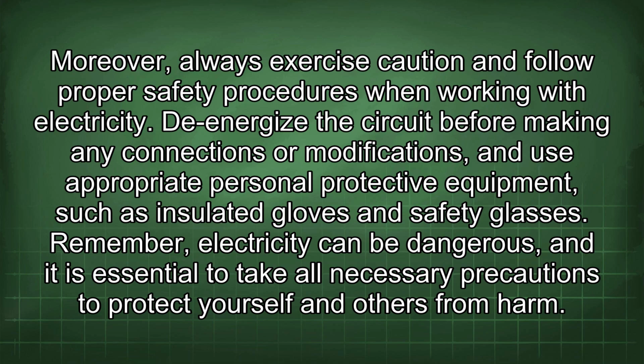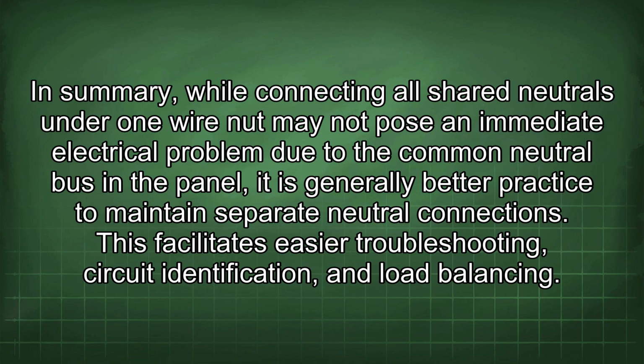In summary, while connecting all shared neutrals under one wire nut may not pose an immediate electrical problem due to the common neutral bus in the panel, it is generally better practice to maintain separate neutral connections. This facilitates easier troubleshooting, circuit identification, and load balancing.